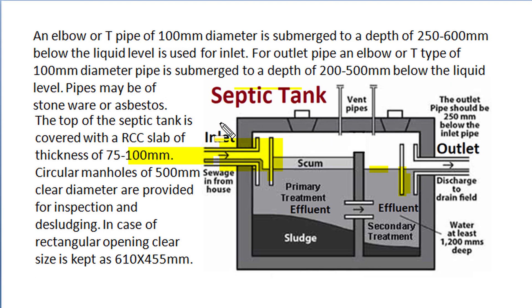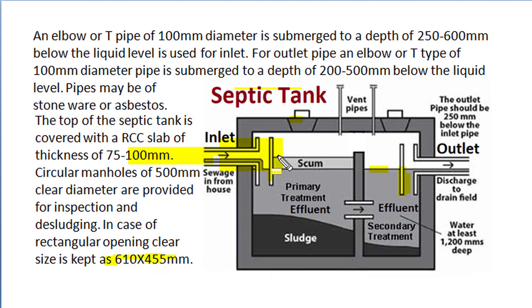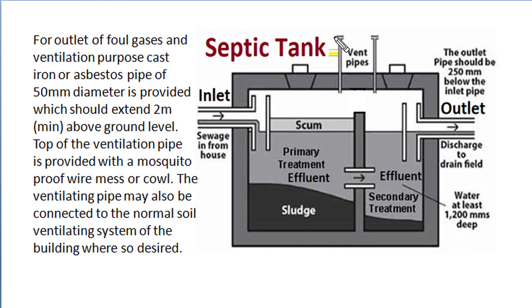A minimum freeboard of around 300 mm should be provided above top water level. The top of the septic tank is covered with an RCC slab of thickness 75 to 100 mm. For cleaning and inspection purposes, circular manholes of 500 mm diameter are provided, and they can be used not only for inspection but also for desludging or emptying of the septic tank. If rectangular openings are used in place of circular manholes, a clear size of 610 mm × 455 mm is required. For outlet of foul gases and ventilation, cast iron or asbestos pipe of 50 mm diameter is provided as vent pipes, and such vent pipes should extend at least 2 metres above ground level. The top of such vent pipe is provided with a mosquito-proof wire mesh or cowl.